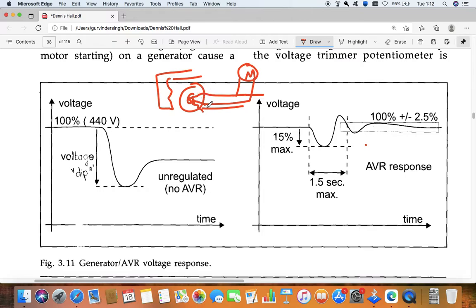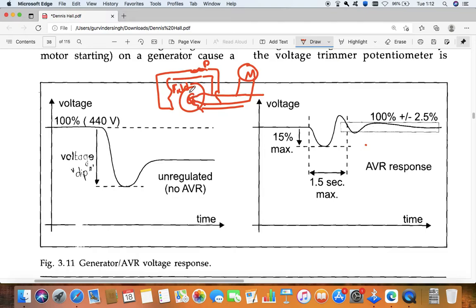Inside the winding of the generator, the voltage dip is there and that dip remains. So we need to increase the voltage. We will need to increase the field excitation. This is the field excitation coil, so we need to increase the field current here. For that we need to use a potentiometer here - we adjust the potentiometer and it will increase the current, increase the field, and the generator voltage will come back to its normal position. But that we need to do manually.